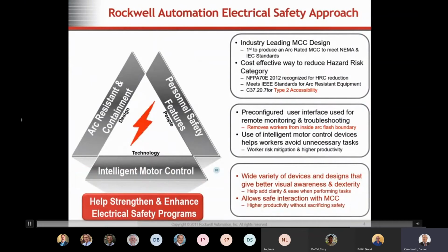All right, this is Rockwell's approach to electrical safety. This basically goes to the three designs I was telling you about. The arc flash containment, which is going to be the arc shield. That's the top one we talked about. That's the medium voltage criteria that it meets. Even though it's low voltage, it's a type 2 accessibility, all four sides. Then we can talk about the IntelliCenter. That's the one we talked about that's going to have an Ethernet backbone for all the intelligent devices. So what that will do is help with remote monitoring and troubleshooting to keep people out of the arc flash zone and minimize risk.